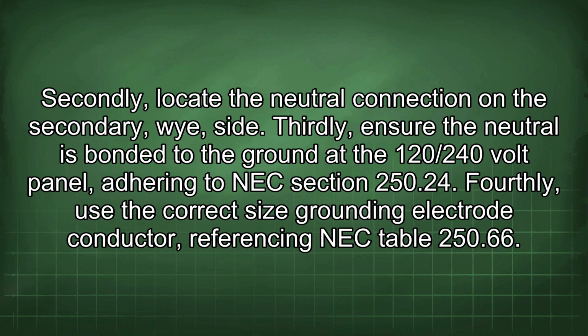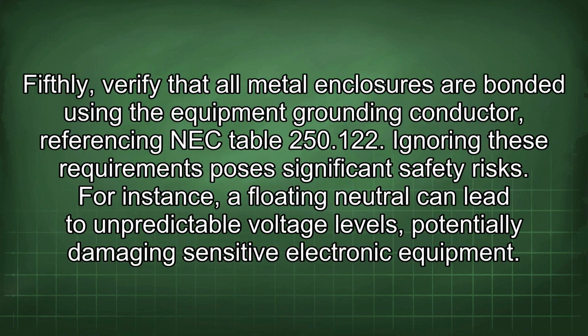Fourthly, use the correct size grounding electrode conductor, referencing NEC table 250.66. Fifthly, verify that all metal enclosures are bonded using the equipment grounding conductor, referencing NEC table 250.122. Ignoring these requirements poses significant safety risks.